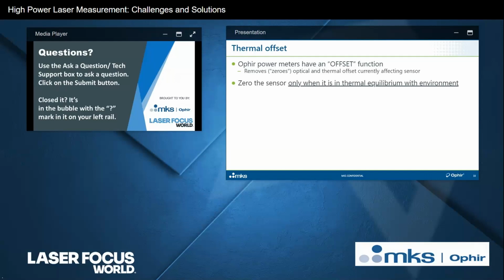I should just mention that the offset caused by the heating of the sensor when the beam is on, you're measuring laser power for hours at a time, the sensor gets kind of hot, so it's radiating heat out into the room, but that's laser beam generated offset, and that's built into our calibration without getting into all the gory details. So if the sensor was in thermal equilibrium with the room, and then you started measuring laser power, so the only heating that took place was because of the laser, then the offset that you pressed at the beginning before you turned on the laser is the right offset that you're going to correctly continue to zero. So that's an important thing to keep in mind, and is generally not so well known, even among seasoned laser professionals. Moving right along.